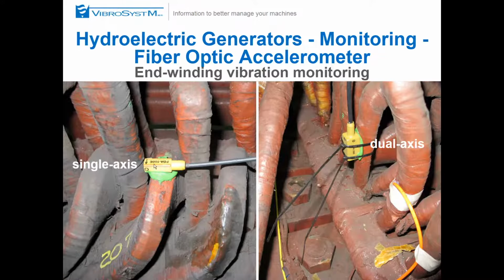Okay, so these are all pictures. Of course the installation is not finished here. When the installation is finished, there are no tie wraps. These are actually covered with resin impregnated tape. So by the end, you can't even see the sensor. That's why I use these pictures, because you actually see the sensor, but when the installation is finished, you can't see a thing. All you see is tape. And that will give you the vibration of this winding in the radial direction and in the tangential direction.